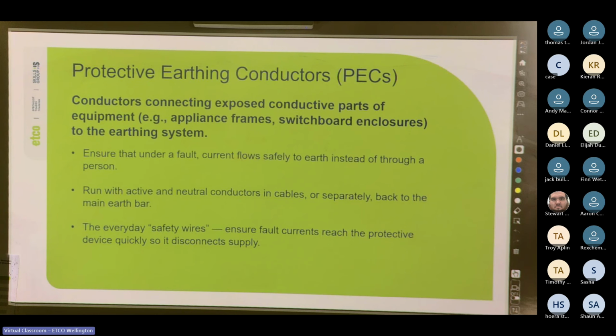And then we have our protective earthing conductors. So think of these as the individual circuit safety line. The main earth bar is your hook-on point, and the socket outlet you work at is you working at height. It's there to stop you from falling and dying. They run to each connection point and into the circuit. So just like a harness, it's going to stop you from dying. It's not going to be pleasant, but it will stop you from dying.